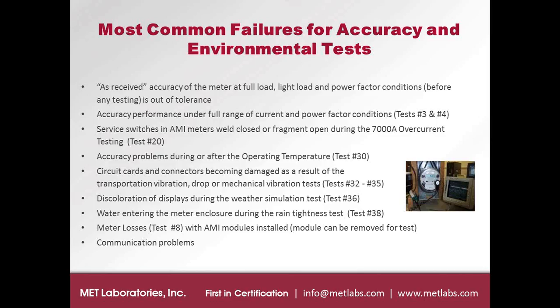Many times we see that the packaging of the product, those two are packaged tests, the package vibration and drop. The packaging, if it's inadequate, you could have damage to the meter, whether you're having tabs break off on external, cracked domes, cards coming loose or breaking brackets internal to the meter, standoffs. We see that sort of damage with improper packaging. The mechanical vibe is really more like an office vibration test. We don't see problems with that too often, although occasionally we will see, say, a larger component shear off of the PCB.